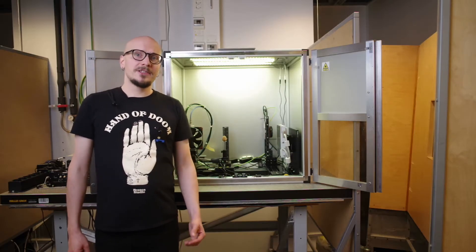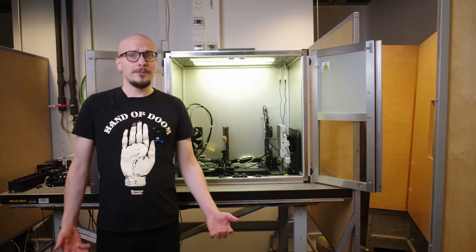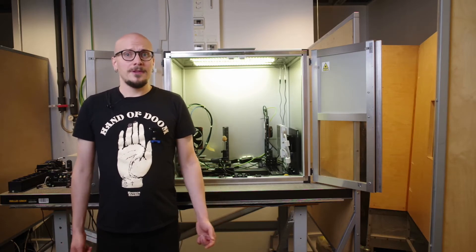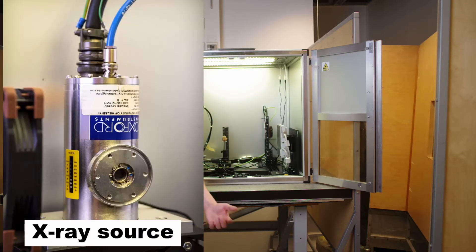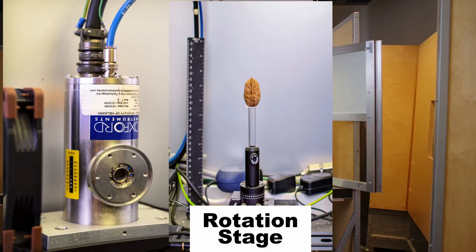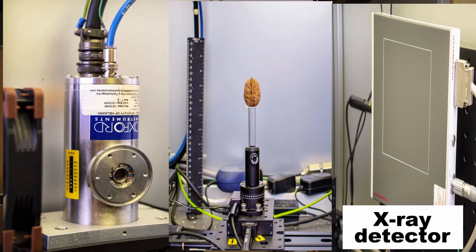The scanner consists of essentially four components: an x-ray source, a sample rotation stage, an x-ray detector, and radiation shielding.